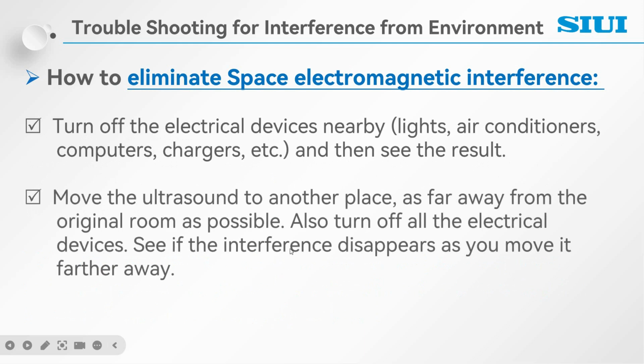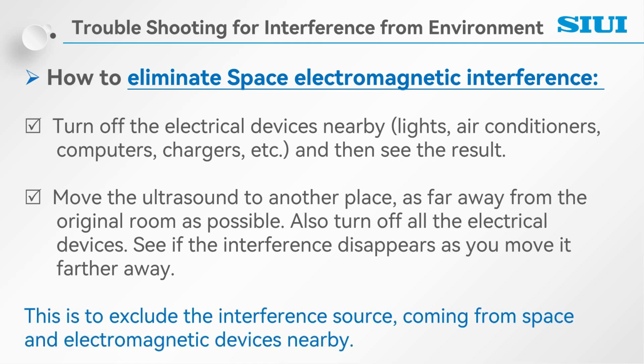These two more steps are to eliminate the space electromagnetic interference. Turn off the electronic devices nearby, for example, lights, air conditioners, computers, chargers, etc., and then see the image result. Also, you can move the ultrasound systems to another place, as far away from the original room as possible. Also, make sure you turn off all the electronic devices in the same room and nearby, and see if the interference disappears as you move it farther away. These two steps are to exclude the interference source coming from the space and electromagnetic devices nearby.